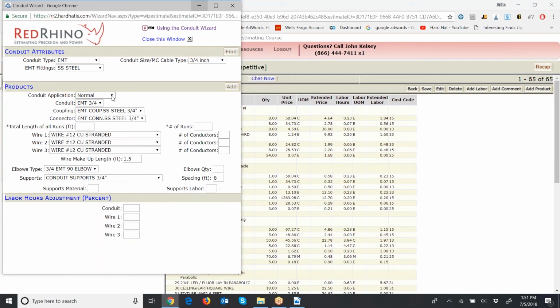So we're going to click the conduit application and set it for plus 10 feet. That means the conduit is above 10 feet off the floor. Next, we're going to put in the total length of all runs. In this case, it was just 20 feet, so we'll type in 20. The number of runs was 2. We want that so the program shows how many connectors are needed.